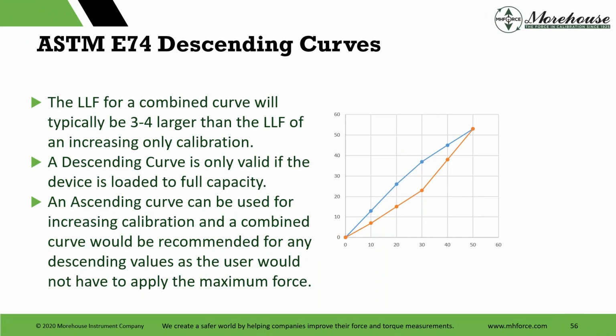Typically, if you need to use a combined curve, why one would do this is they might say, hey, I just want to go to 30% and back down. That's fine. But to do that, you're going to have to take the penalty of fitting the entire curve. So the LLF for a combined curve will typically be 3 to 4 times larger than the LLF of an increasing only calibration. We just showed the difference was 0.05.